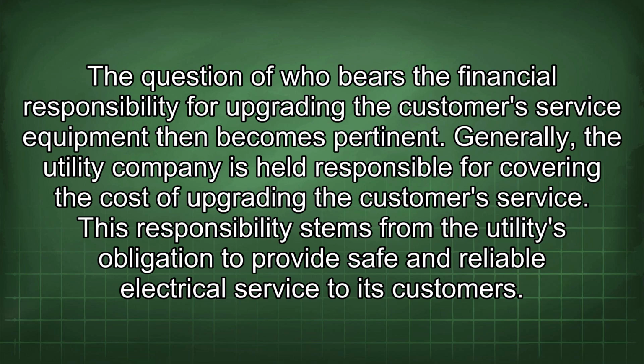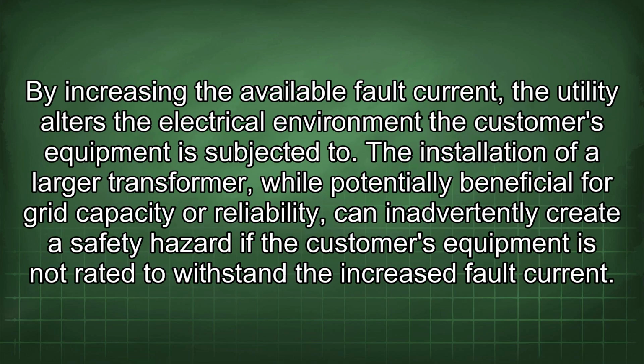Generally, the utility company is held responsible for covering the cost of upgrading the customer's service. This responsibility stems from the utility's obligation to provide safe and reliable electrical service to its customers. By increasing the available fault current, the utility alters the electrical environment the customer's equipment is subjected to. The installation of a larger transformer, while potentially beneficial for grid capacity or reliability, can inadvertently create a safety hazard if the customer's equipment is not rated to withstand the increased fault current.